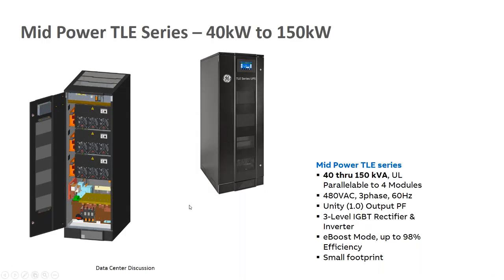So just quickly going through the ABB UPSs. There's the smallest member, and this is on the 480 volt, talking data centers, so small data centers and above, is what we call the mid-power TLE. It's available from 40 kW up to 150 kW. All of the UPSs, whether monolithic or modular, are IGBT-based rectifier and inverter. High efficiency, power factor corrected on the input, like a unity power factor rated. Can do economy mode, or e-boost is another name for economy mode. So the mid-power TLE from 40 to 150 kVA.